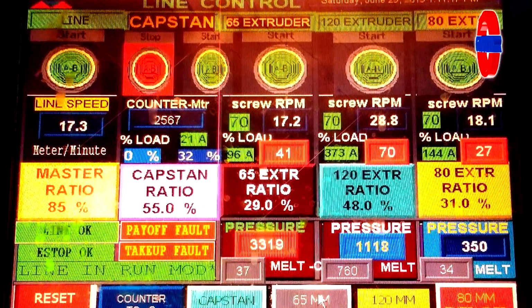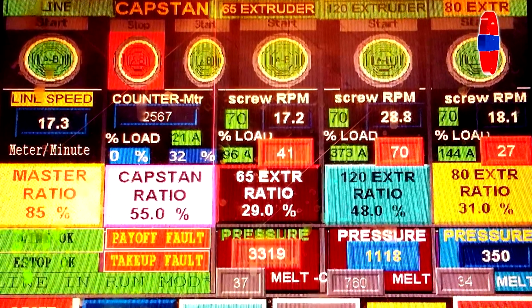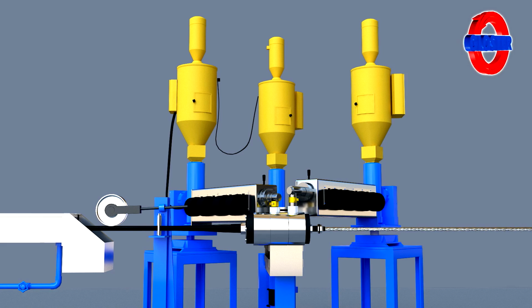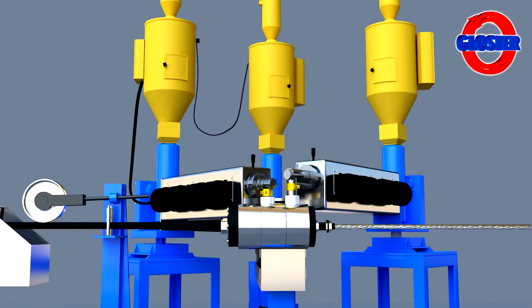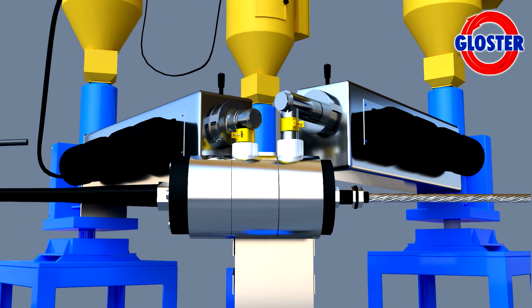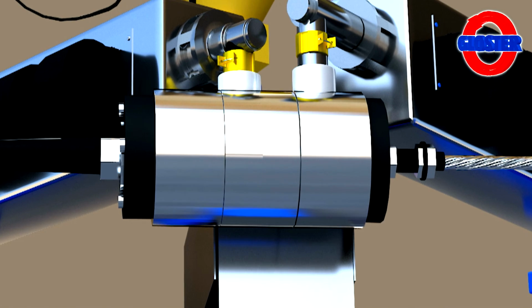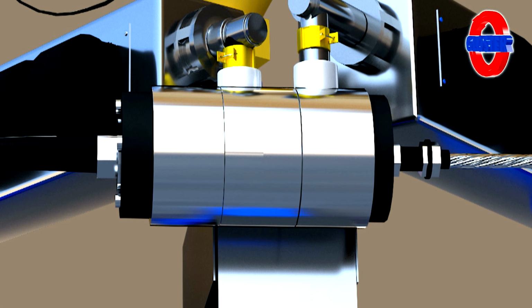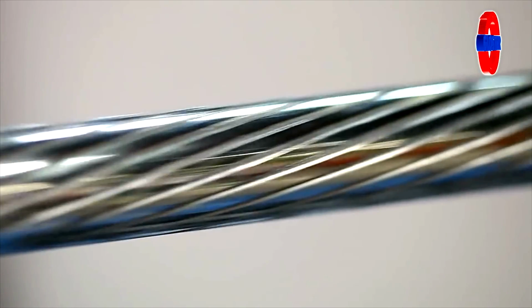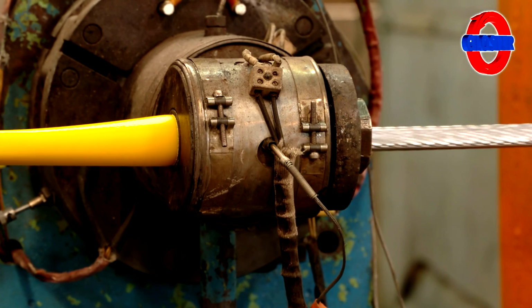Automatic diameter controller maintains the diameter of the cable from start to finish. This machine is fitted with a laser diode sensor to control variations in diameter through commands into the computer of the automatic diameter controller. By automatically varying the speed of the extruder, the computer rectifies variations, if any, in the diameter of the cable.